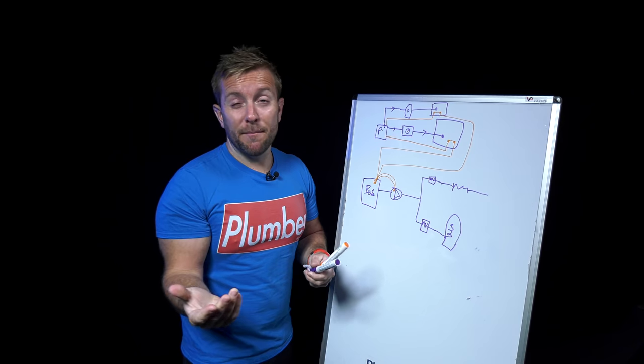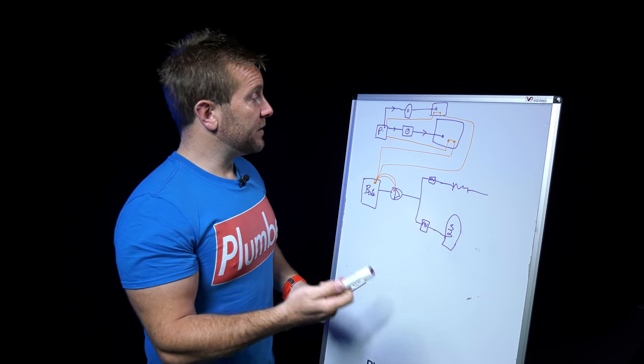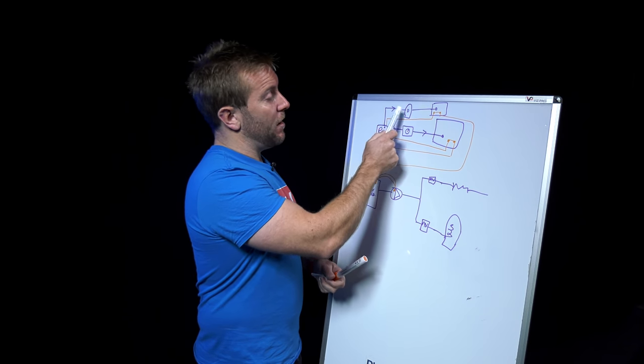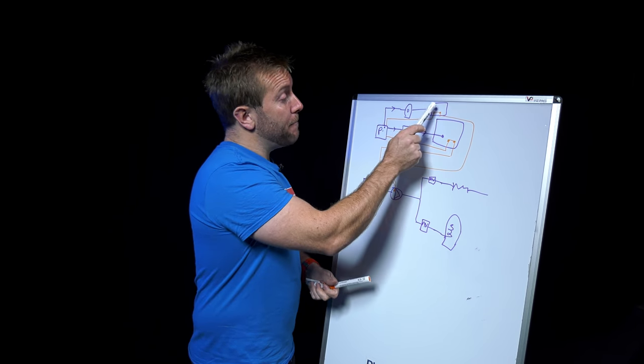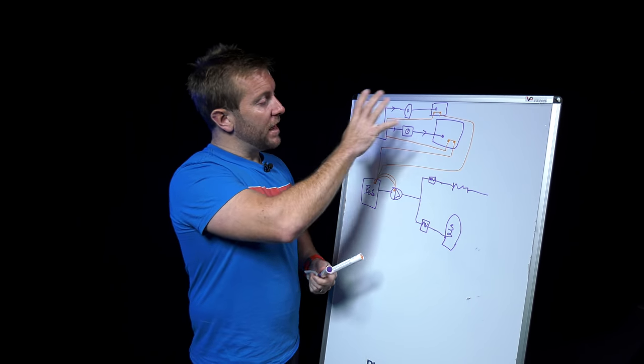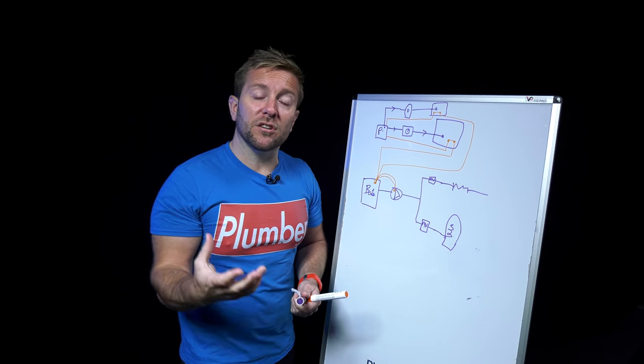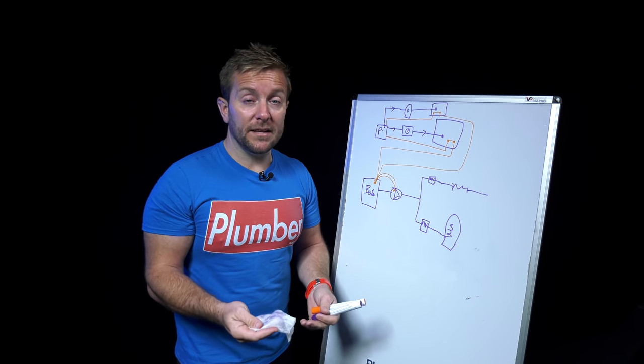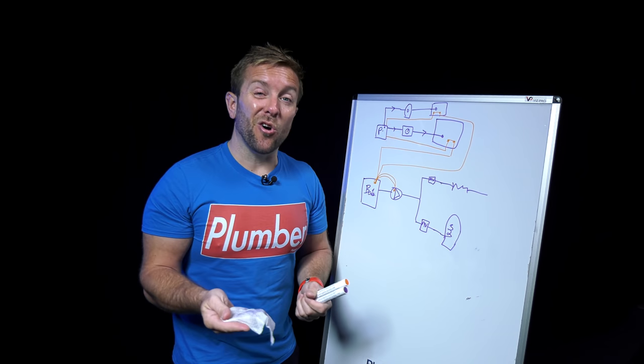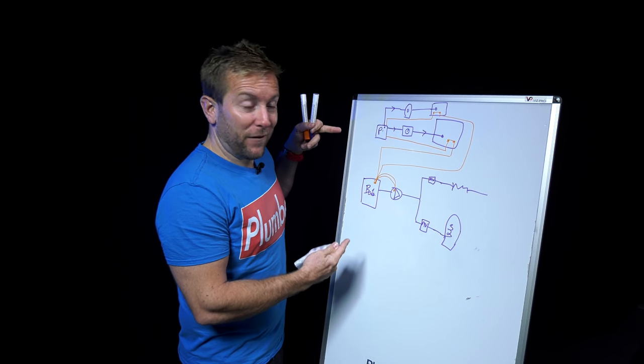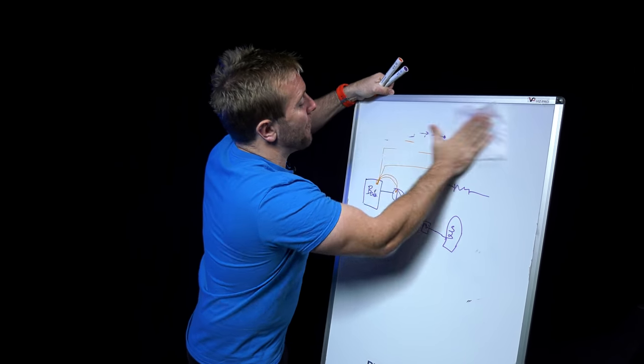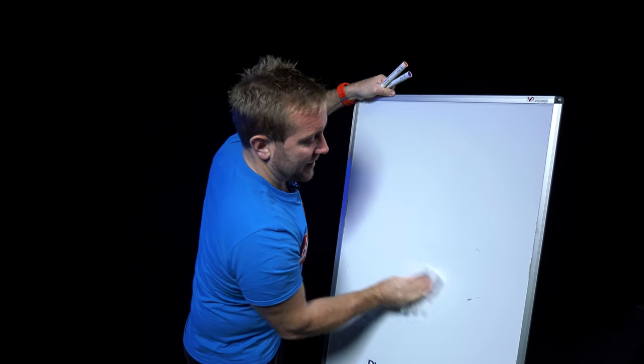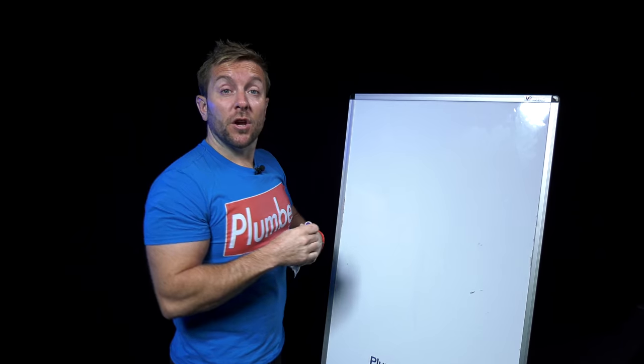Without going into too much detail, three port valves have a slightly more complicated switch assembly. But just see it like this: the valve needs to open and it needs to tell the boiler and the pump that it is open so it's safe for everything to come on. Once that little switch in there is live, it's going to send a live supply to our boiler and it's just going to hop the same supply over to our pump. So that is how we initiate a live supply in a schematic way over to our radiators when it wants to come on.